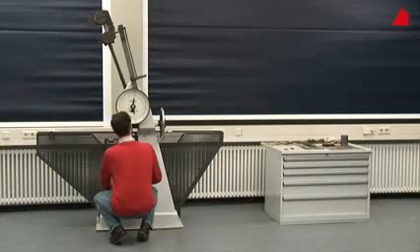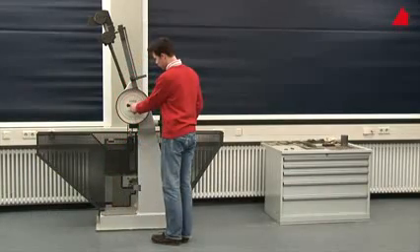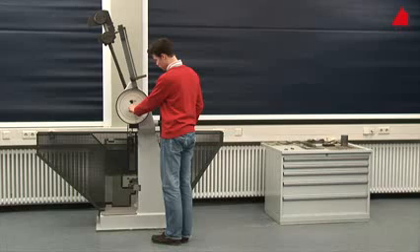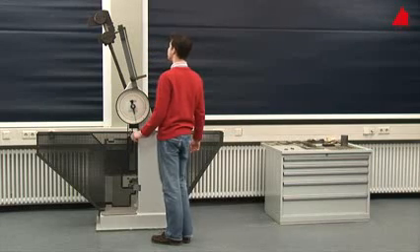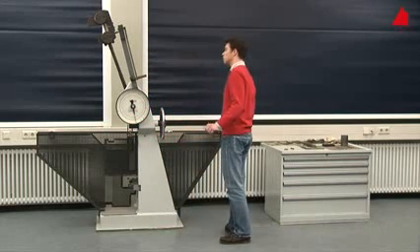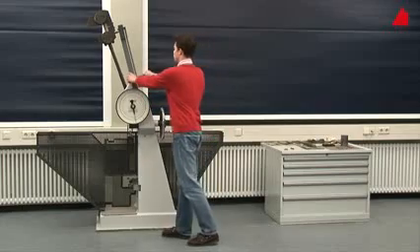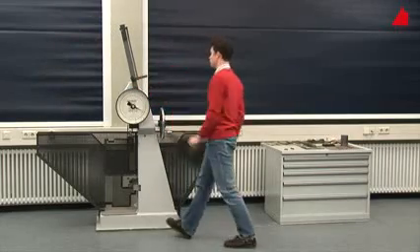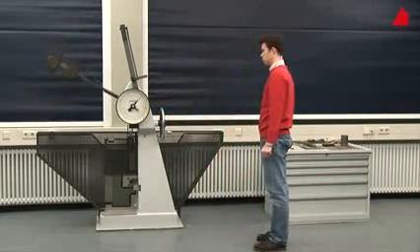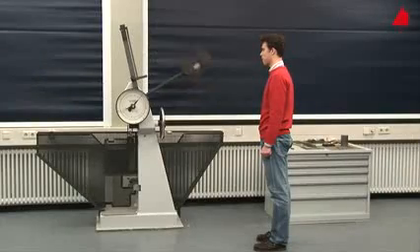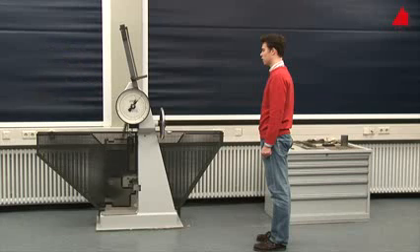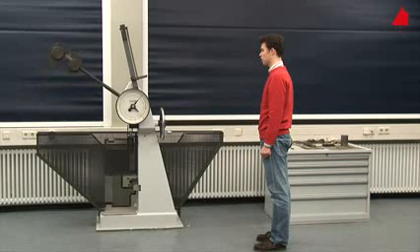Next, he turns the drag indicator downwards again and checks that everything is prepared correctly. The test can begin. The pendulum is released, swings downwards, and hits the specimen with its rounded hammer pin. The specimen absorbs part of the pendulum's energy, so the pendulum doesn't reach the full height on the other side.